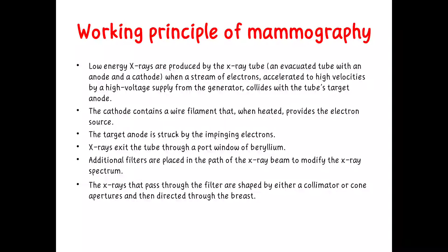Additional filters are also placed in the path of the X-ray beam. Why are filters placed in the path of the X-ray beam? To modify the X-ray spectrum or to modify the X-ray beam. The X-rays that pass through the filter are shaped by either a collimator or cone apertures, and further directed through the breast. That means there is one device attached to the X-ray tube, known as the collimator, and the basic function of this collimator is to provide shape and size to the X-ray beam.